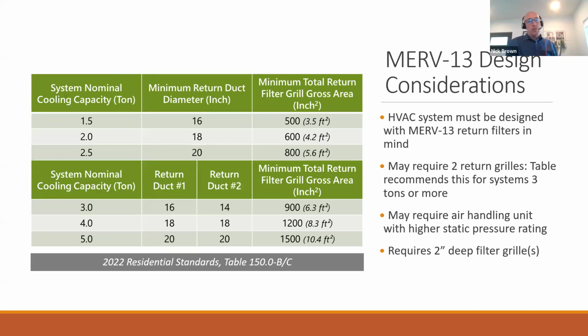This table gives best design practices for return grill sizing. If designed to this table, your system does not require one of those HERS verifications, fan watt draw. So that's a nice incentive, but you'll notice it tells you the duct diameter and the total filter grill required according to the tonnage of your ducted system. And once you hit 3 tons, it's calling for 2 separate returns. I don't see 3-ton systems designed that way yet, but based on the building science, this is the way we should be doing it.